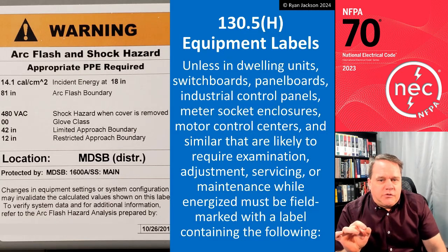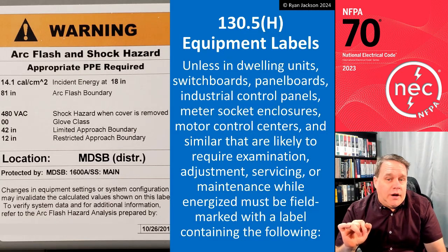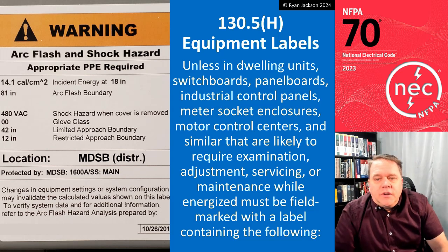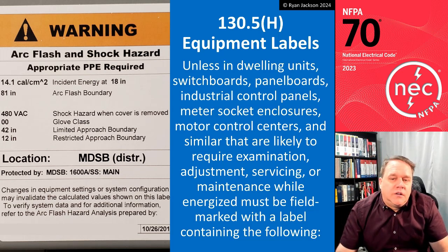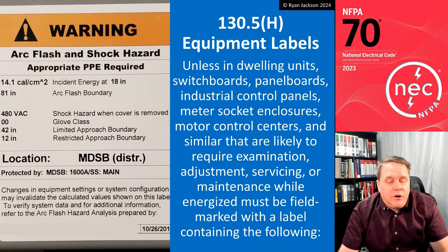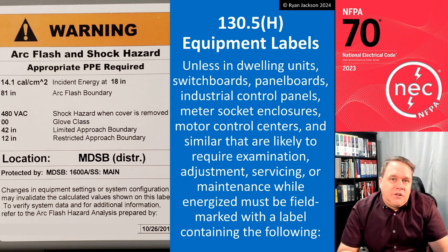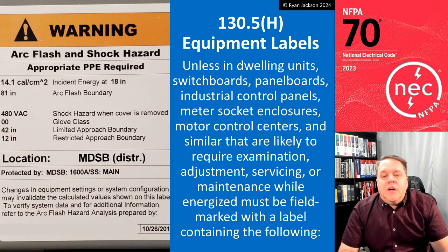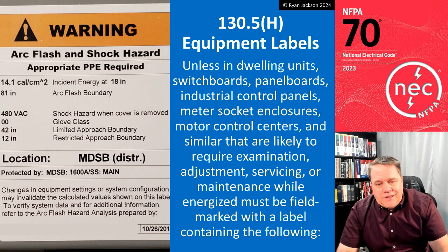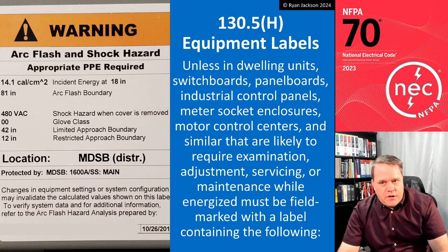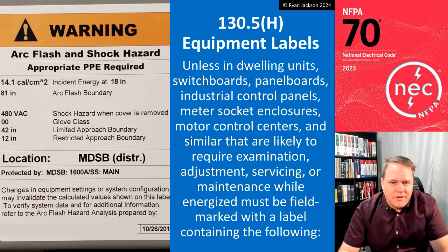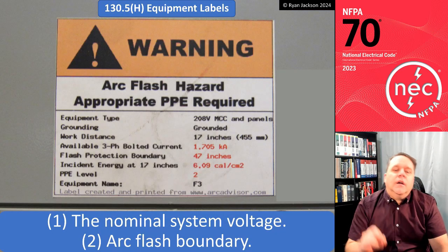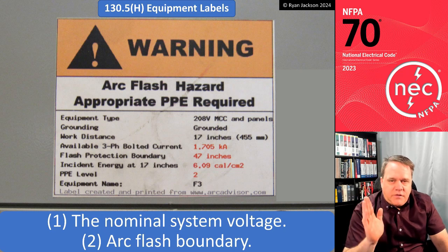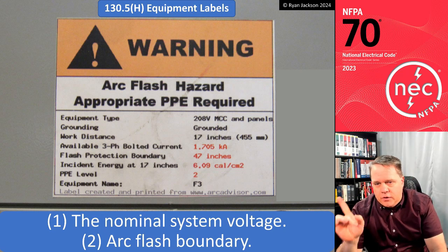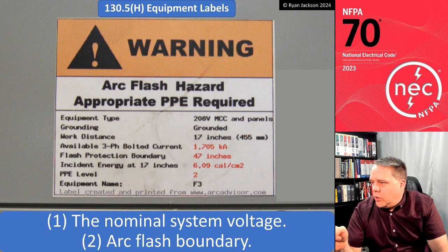130.5(H), equipment labels. Unless located in dwelling units, switchboards, panelboards, industrial control panels, meter socket enclosures, motor control centers, and similar that are likely to require examination, adjustment, servicing, or maintenance while energized must be field marked with a label containing the following information. All right, so what does the label have to say? Number one, always got to tell me the voltage. All right, so here it says 208 volts.